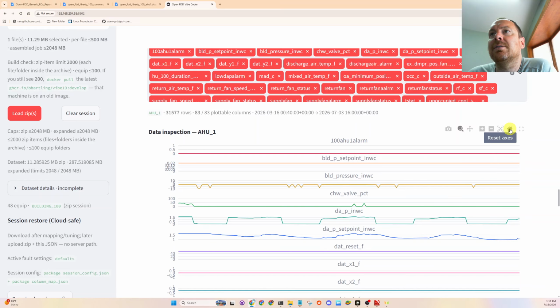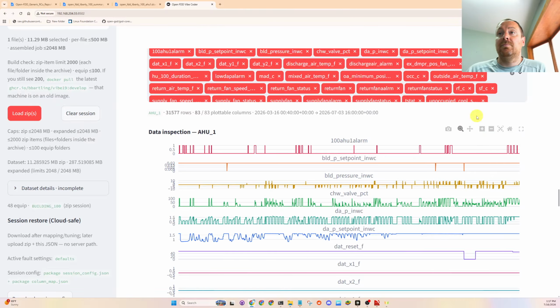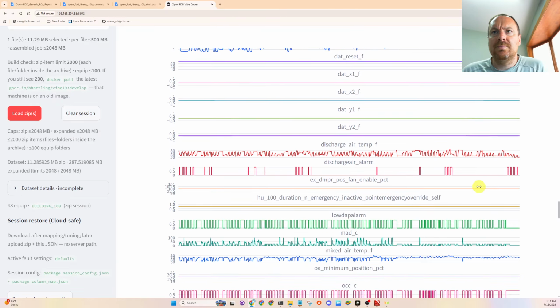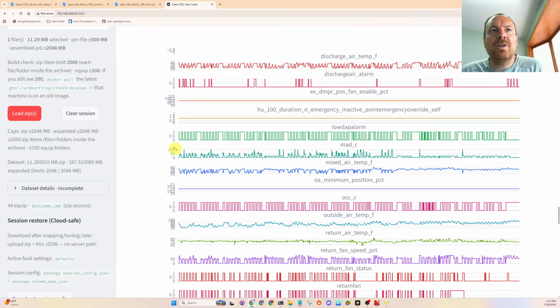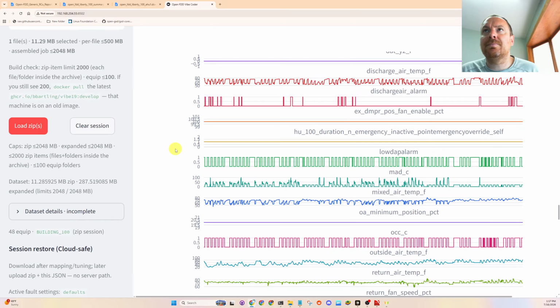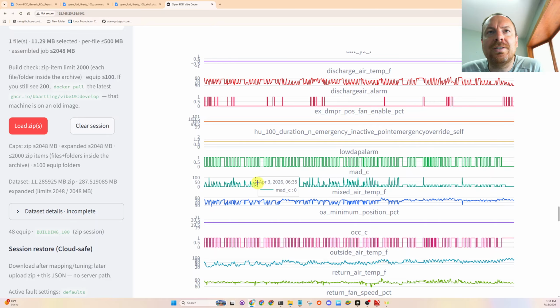Let's go back. Let's reset the axes. Okay, so this is probably hard to see from where you guys are, but you can kind of see a general trend in the data that we started at the end of heating season, and then we're in full mechanical cooling season, and it's very 0 to 20%, 0 to 20%, a little teeny dip of economizing right there. But then in the middle, so this would be March, April, May, June, we start seeing this hot weather, which we would expect to see. And we're almost at just minimum position. So that's good. That's a very nice thing to view.